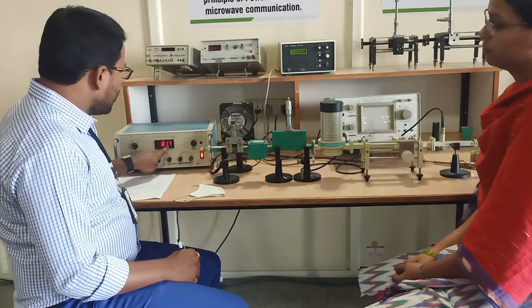And see the current, the beam current should not exceed 18 milliamps. Then select the repeller. By rotating the repeller knob in the anti-clockwise direction, fix the maximum signal strength on the CRO screen. See here, you have to fix the maximum signal strength that appears on the CRO screen.